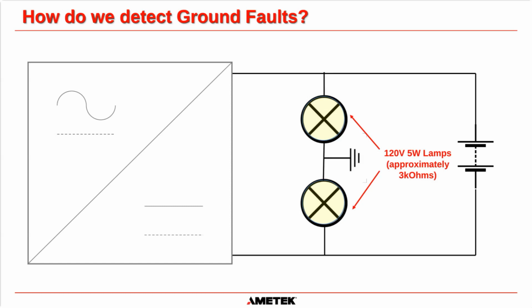The circuit on your screen is the simplest form of ground detection that you can get. All you do is you put two lamps connected in series, in parallel with the charger, if that makes sense. Then you connect the center point of those two lamps to ground. Now, if it's a 5-watt lamp, you can use Ohm's law, and that works out that the resistance of each lamp is 3K.